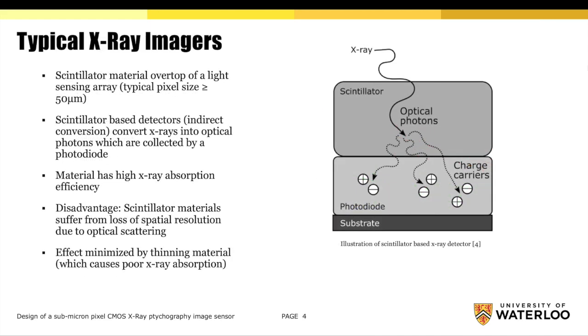X-ray imaging devices usually incorporate a light sensing array and an x-ray sensitive scintillator material. These scintillator-based detectors convert x-ray photons into optical photons, and these optical photons are then collected by a photodiode.